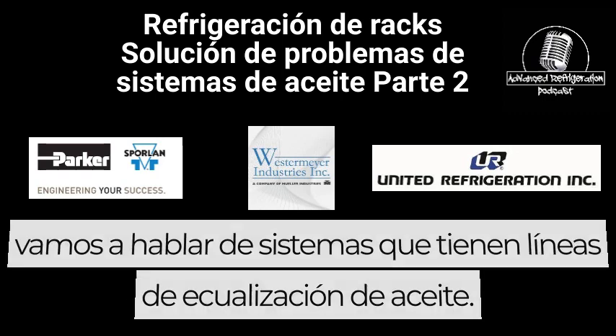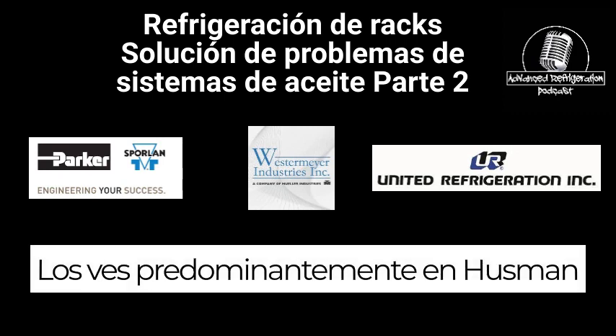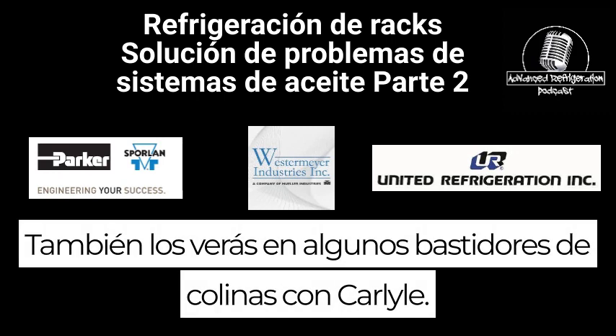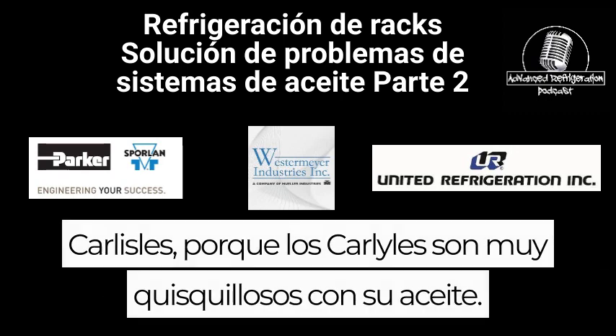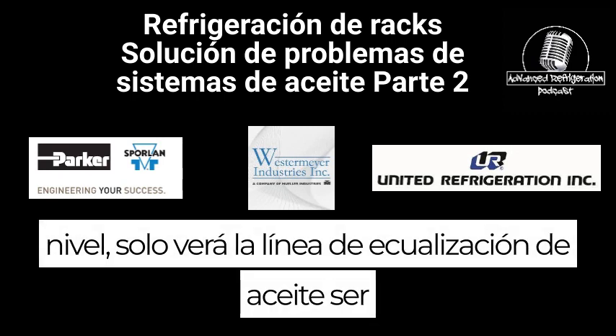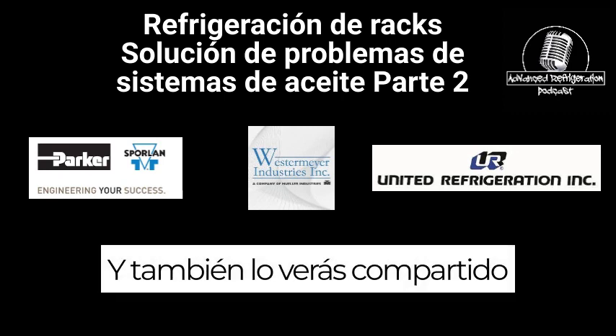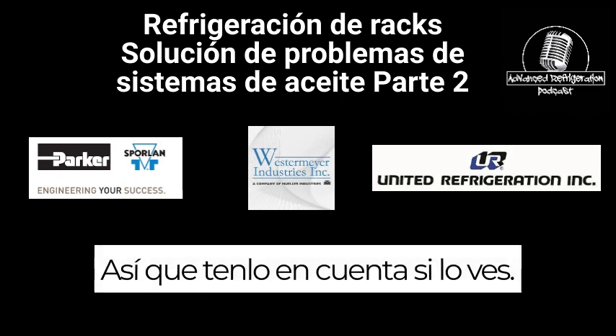All right, we're also going to talk about systems that have oil equalization lines. You see these predominantly on Hussmann racks that are utilizing Copeland compressors. You'll also see them on some Hill racks with Carlisle. When they're hooked up between the Carlisles, because Carlisles are very finicky with their oil level, you'll only see the oil equalization line shared on the same suction. And you'll also see it shared on compressors of similar heights. So be mindful of that.